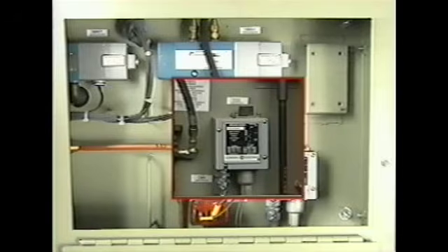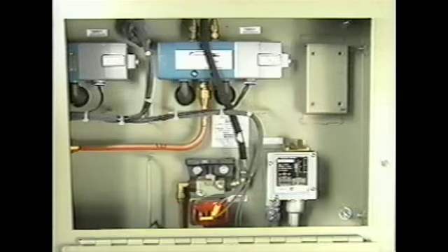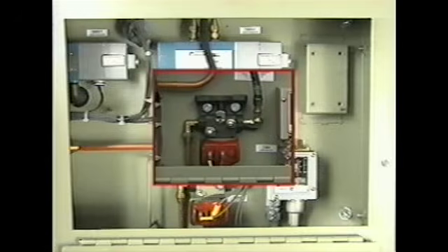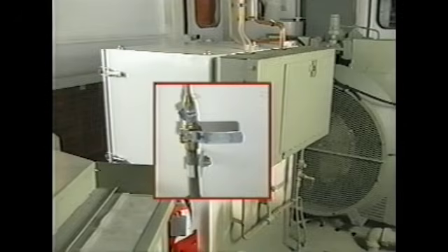The compressor governor switch, CGS, provides an input signal to the X controller for the operation of the air compressor. The compressor magnet valve is used to load the air compressor during pumping operation. The compressor cutout cock is used for maintenance.